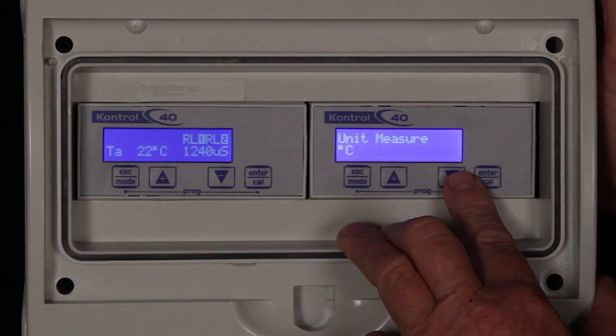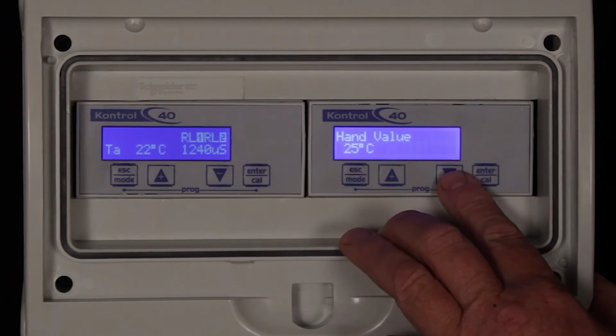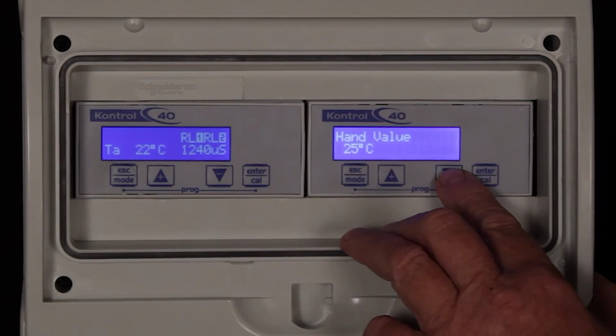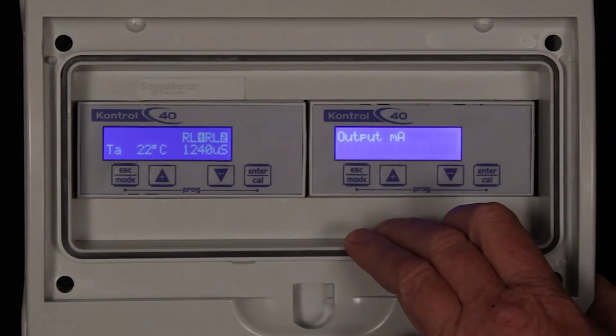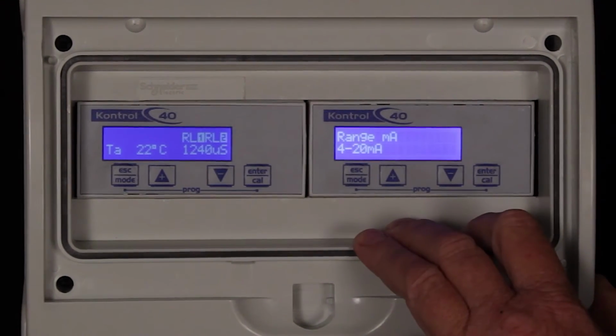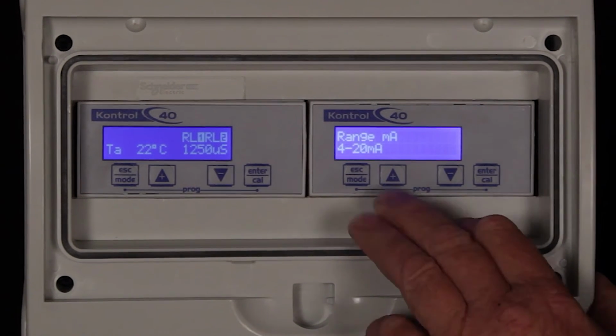Once again, the temperature is set to degrees Celsius. The hand value is set to 25 degrees Celsius, for we do not have temperature compensation on this controller. The output range is set to 4 to 20 milliamps. A value of 4 pH is 4 milliamps and 14 pH is 20 milliamps.